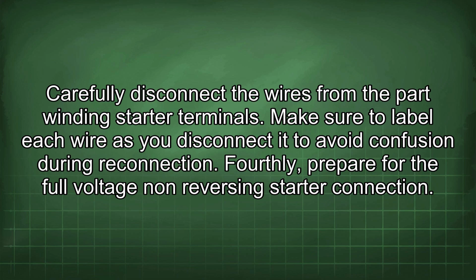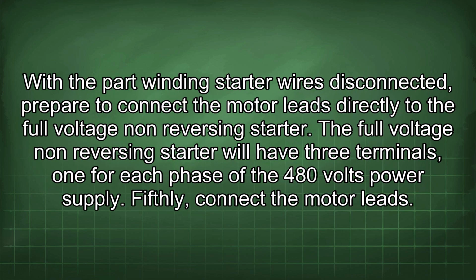Make sure to label each wire as you disconnect it to avoid confusion during reconnection. Fourthly, prepare for the full voltage non-reversing starter connection. With the part winding starter wires disconnected, prepare to connect the motor leads directly to the full voltage non-reversing starter. The full voltage non-reversing starter will have 3 terminals, one for each phase of the 480 volts power supply.